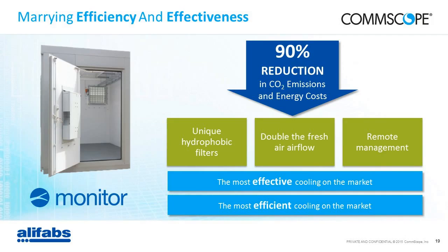We propose double the fresh air airflow. So we have up to 3 fans delivering each 1,500 cubic meters per hour. We have a system that can deliver up to 5,000 cubic meters per hour on 48 volt DC. And this is not what the fans deliver in empty space. This is what the fans actually deliver in the unit. And again, this is something very important that many manufacturers often specify as a given, but this is what our system actually delivers. So finally, that makes it the most effective system because of higher airflow.